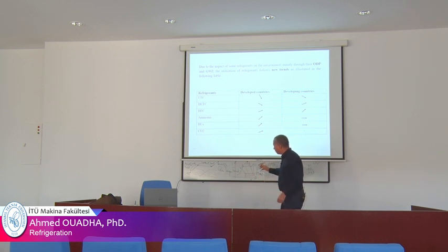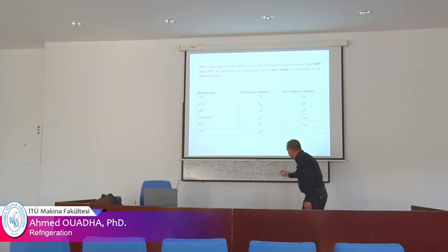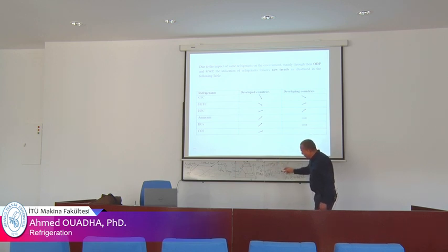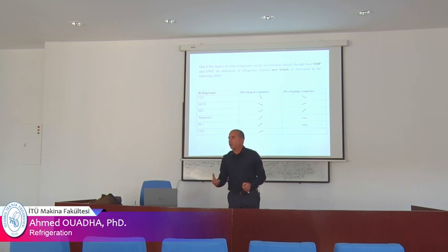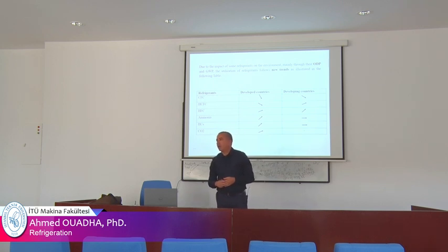Carbon dioxide has a critical temperature of about 32, so we can't use it like this. So we use it in what we call a transcritical cycle, like this. It means a cycle that develops on both sides of the critical point, a part here, a part here. This is carbon dioxide. They use it for air conditioning for cars and for commercial refrigeration. And especially in Norway, in Sweden, I don't know Germany, but in Norway, they are leaders in the utilization of carbon dioxide as refrigerant in transcritical cycles.